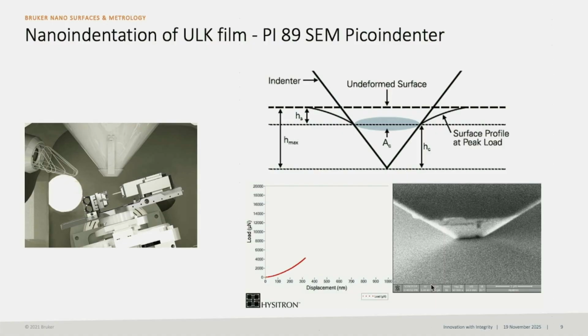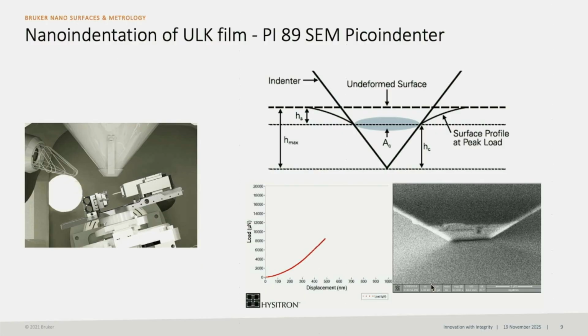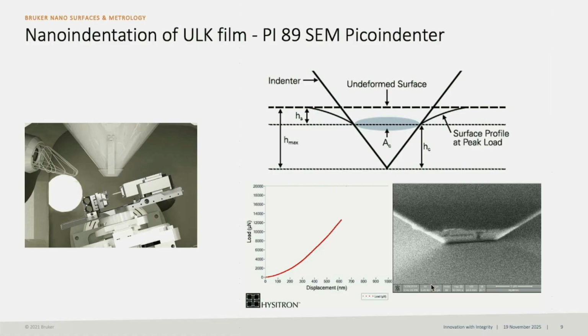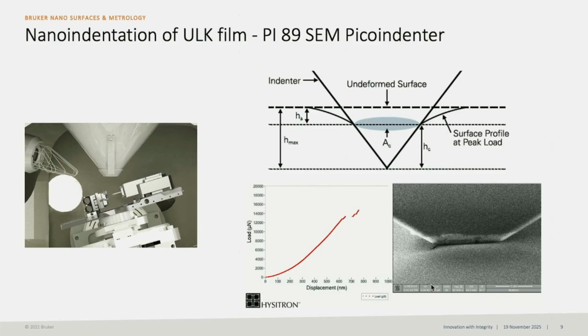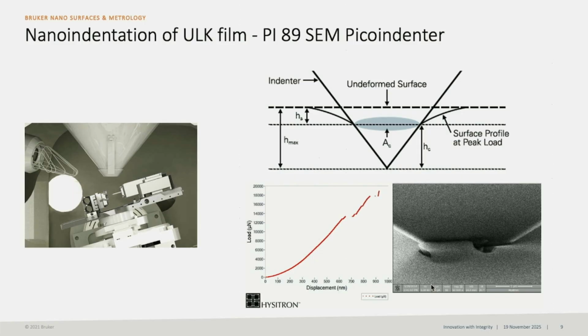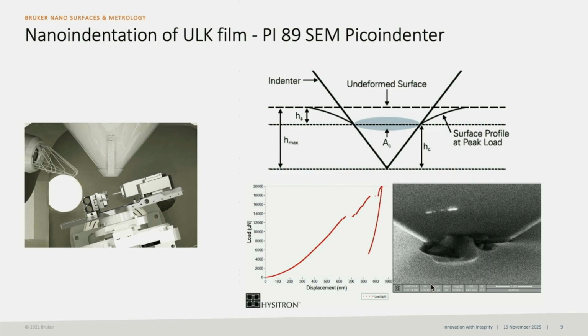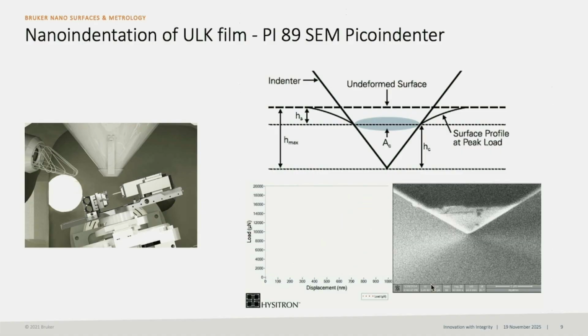So there is another example for the nano indenter on the same thing. You look at this, this is our machine inside of the SEM, right? We tilt the angle, then we can see the indenter and the tip. With the nano indenter, we can measure the hardness and modulus by the mechanical model, but sometimes we can see some strange signal in our force displacement curve.